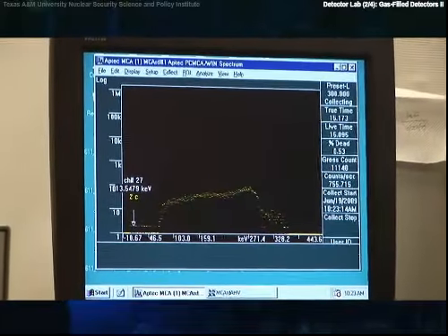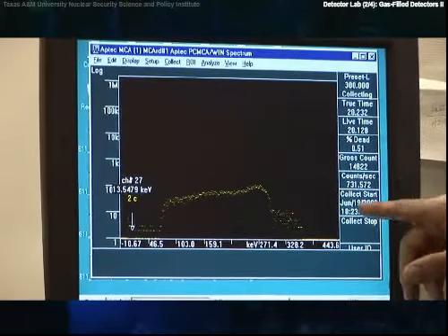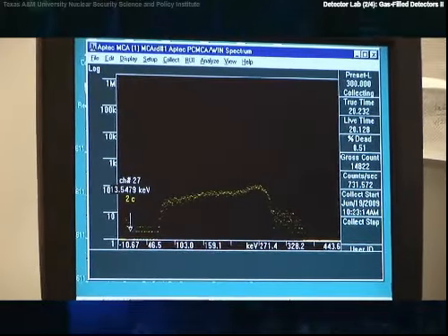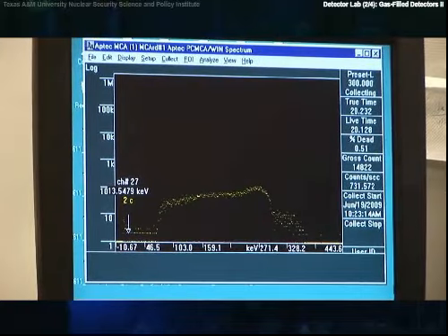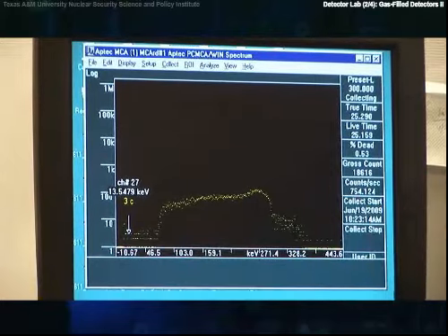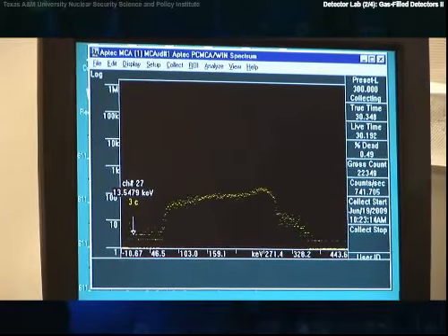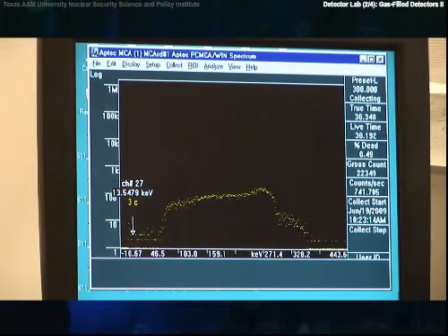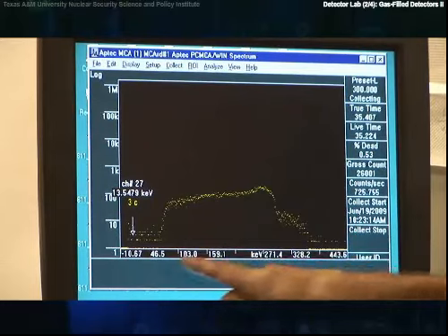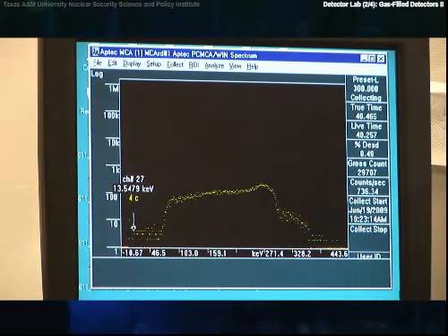The reason we tortured you with statistics earlier is you know that these are Poisson distributed in each channel. But let me point out here, this is the full energy peak right here. This is where both the alpha and the lithium-7 deposit all their energy into the gas. This is gamma contamination way down here, and you can tell we don't have very much.